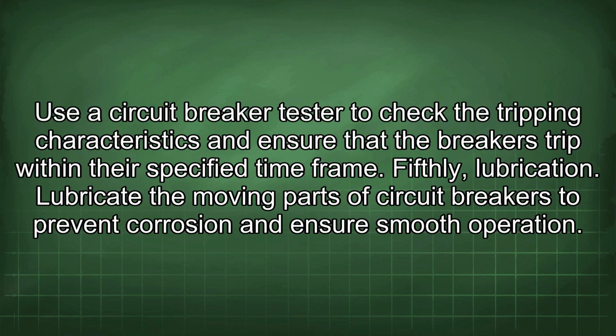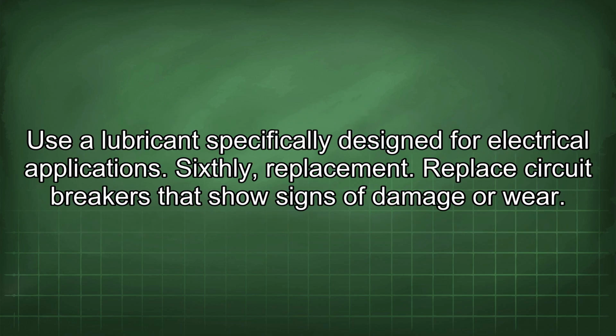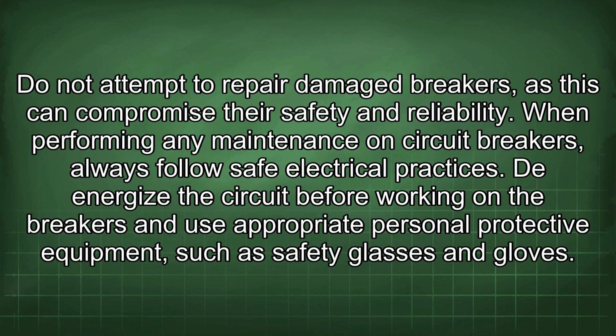Use a circuit breaker tester to check the tripping characteristics and ensure that the breakers trip within a specified time frame. Fifthly, lubrication. Lubricate the moving parts of circuit breakers to prevent corrosion and ensure smooth operation. Use a lubricant specifically designed for electrical applications. Sixthly, replacement. Replace circuit breakers that show signs of damage or wear. Do not attempt to repair damaged breakers, as this can compromise their safety and reliability.